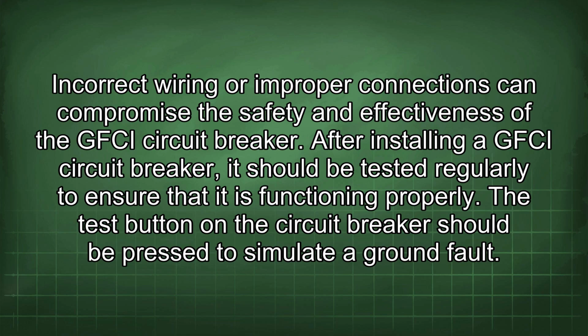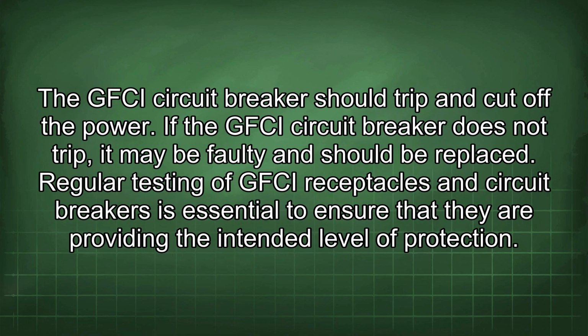After installing a GFCI circuit breaker, it should be tested regularly to ensure that it is functioning properly. The test button on the circuit breaker should be pressed to simulate a ground fault. The GFCI circuit breaker should trip and cut off the power. If the GFCI circuit breaker does not trip, it may be faulty and should be replaced.